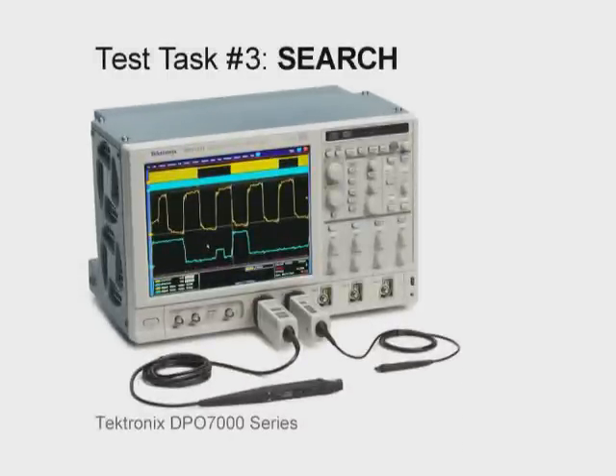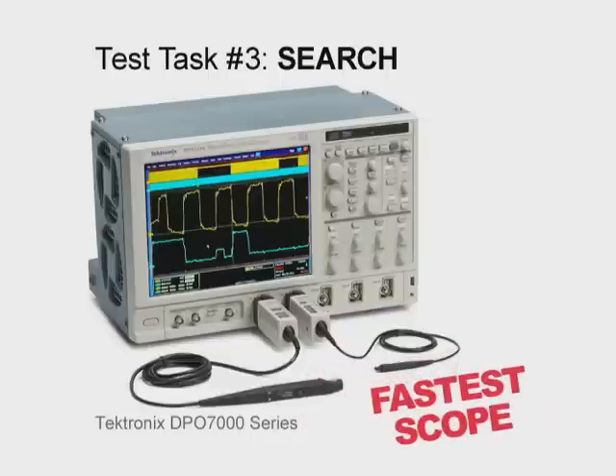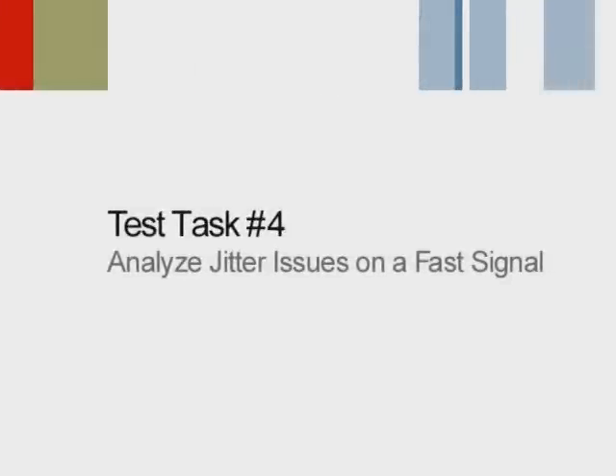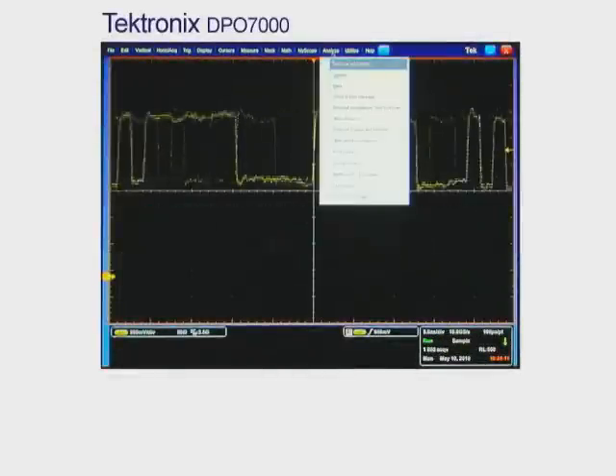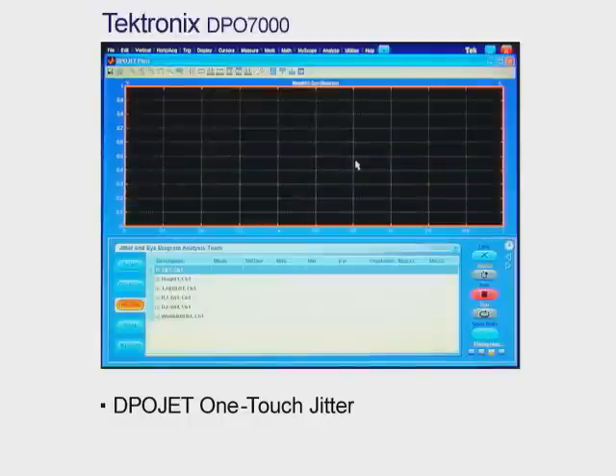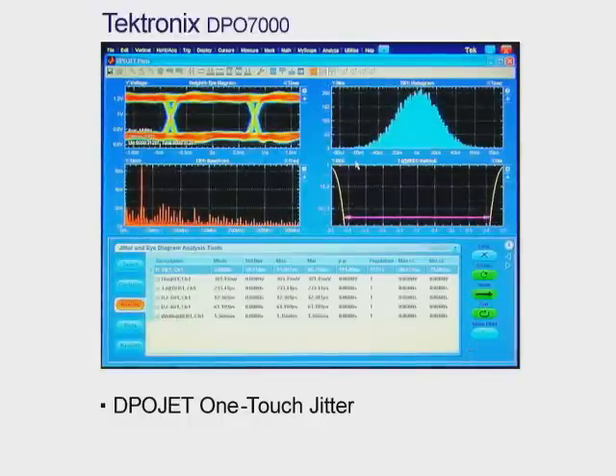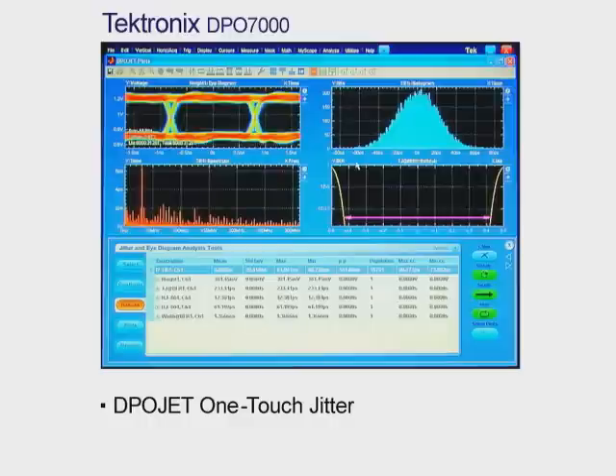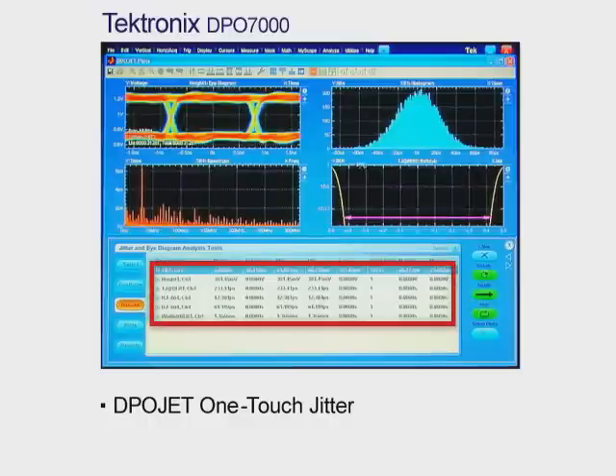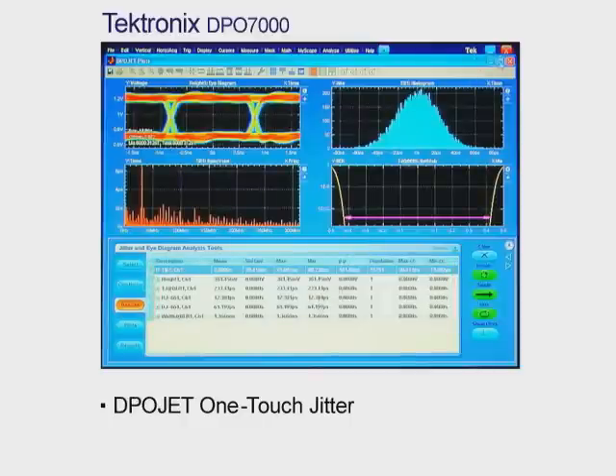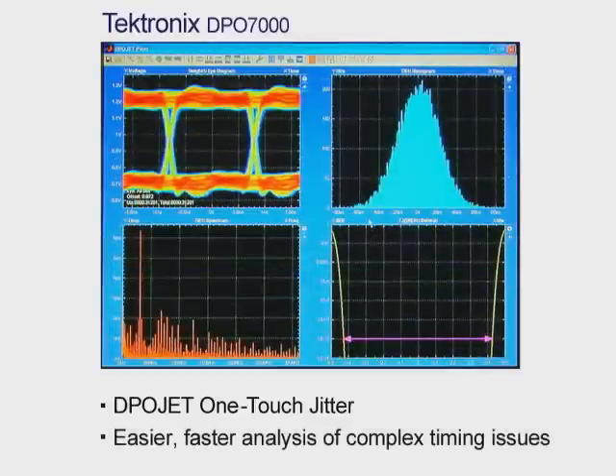After performing test task number three to search for specific events of interest, searching for and finding specific setup and hold violations is easiest and fastest with the Tektronix DPO7000. For our final task, let's perform a jitter measurement to analyze that 622 megabit per second signal to identify potential timing errors. With the Tektronix DPO7000, we can quickly perform jitter analysis using DPO Jet's one-touch jitter. With a simple menu selection, we can get a complete four-plot view of the eye pattern, histogram, frequency plots, and bathtub curve of the 622 megabit per second signal, and dig even deeper using the additional measurement analysis data shown. With the Tektronix one-touch jitter capability, performing complex timing analysis is easier and faster than ever.